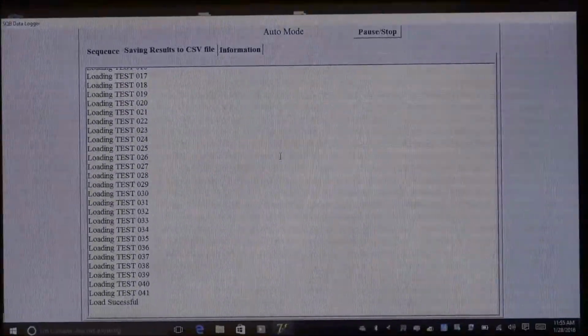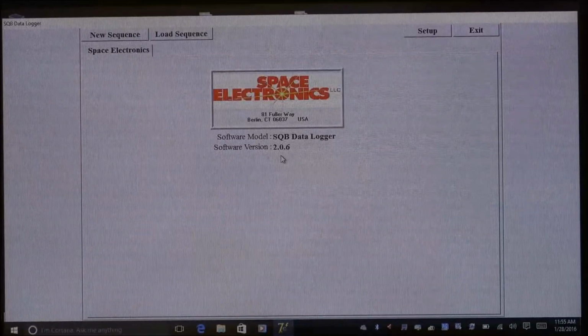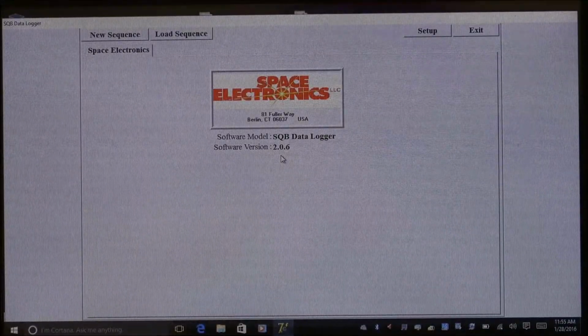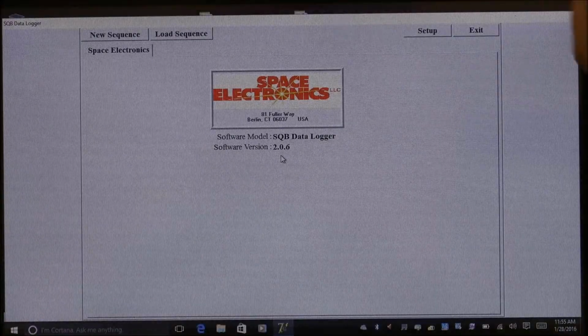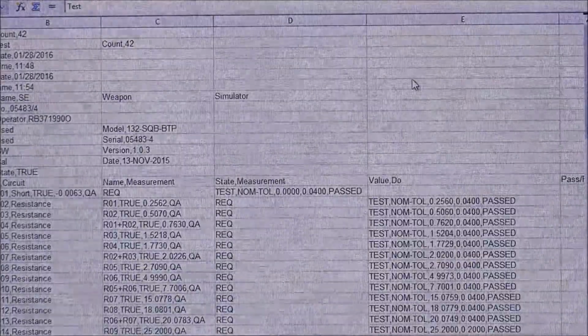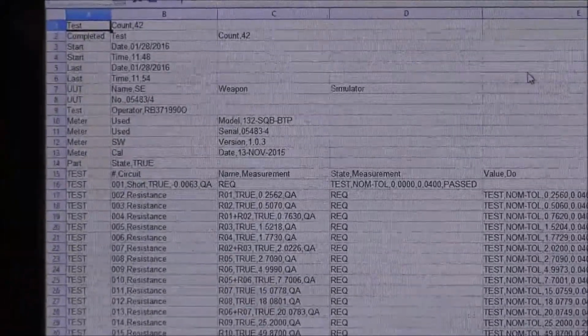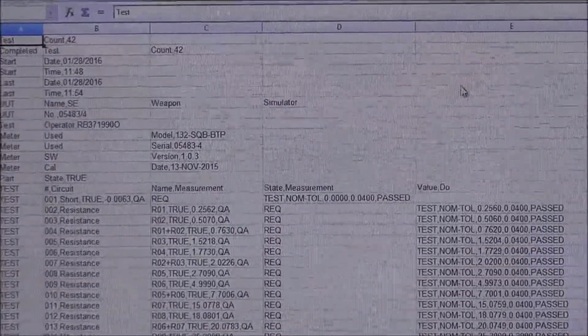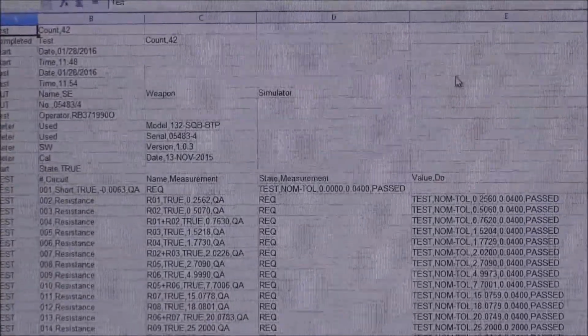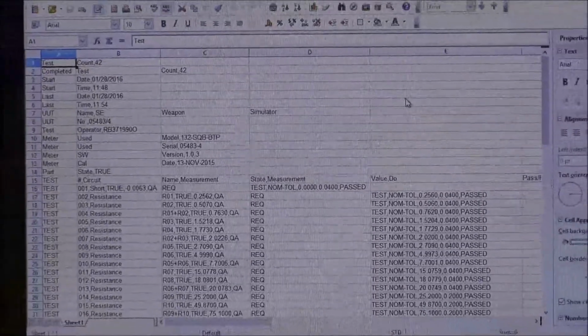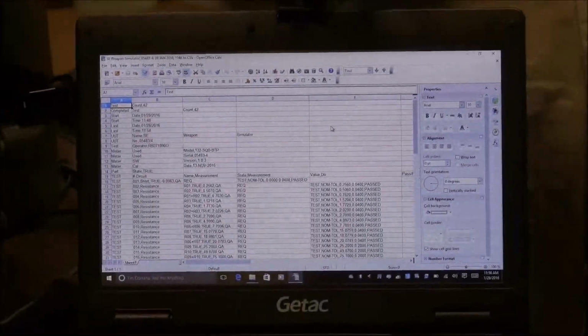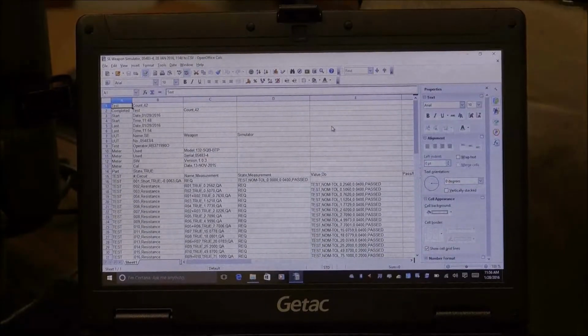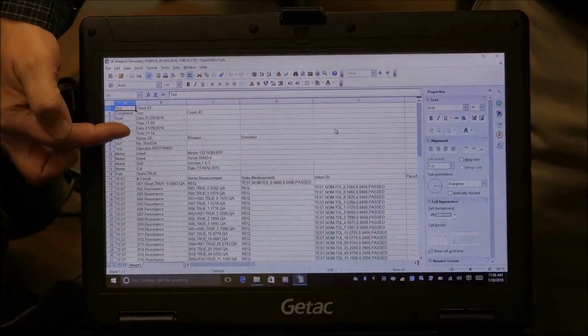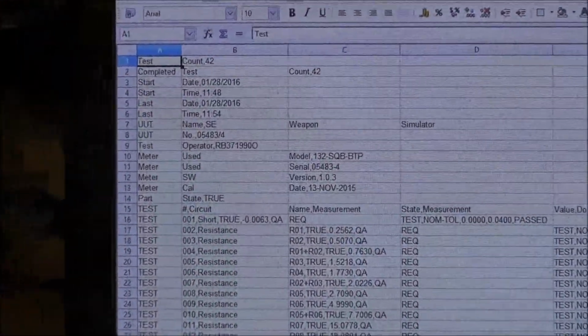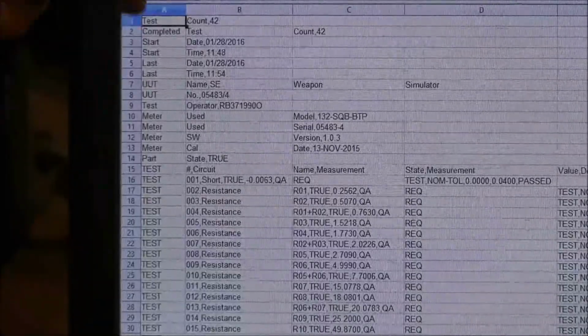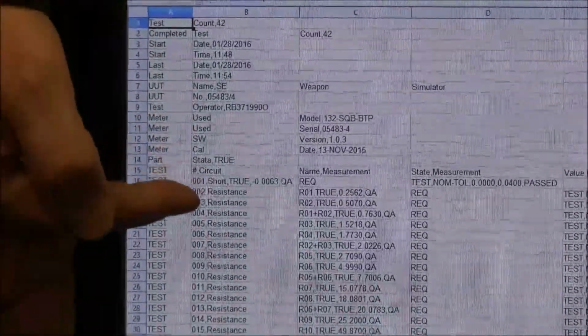This software is automatically set up to save the CSV file at the end of every test. So you always have a history of what tests have been done. So this is the CSV file that gets outputted automatically from our system. It goes into a results folder, which can be interrogated through a network device if this is in a rack and tied to the network, or it can be copied from this onto a thumb drive and put onto a computer where you can store it and analyze it. Basically it shows information about when the test was done, what was tested, what was the calibration date of the equipment that was used, what was the serial number of the equipment that was used, and then the tests themselves.